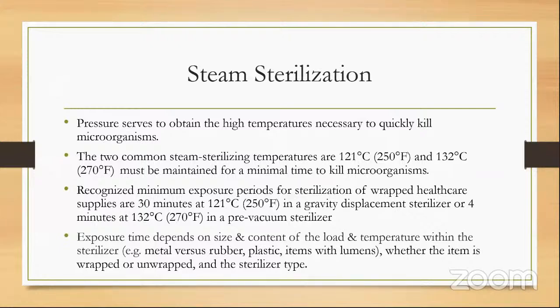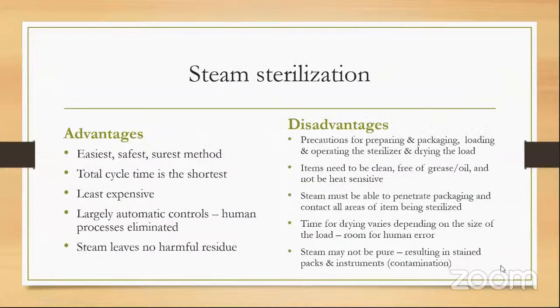Of course, the exposure time depends on the size and content of the load and the temperature within the sterilizer. So whether it is metal or rubber or plastic, or if the items have lumens, whether the item is wrapped or unwrapped, and the type of sterilizer, all of those will determine the length of exposure.